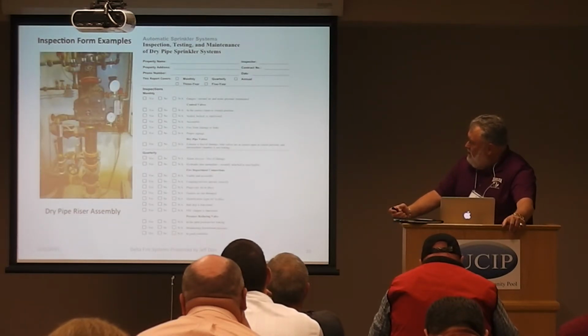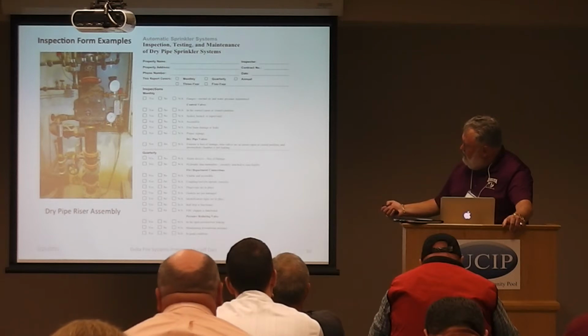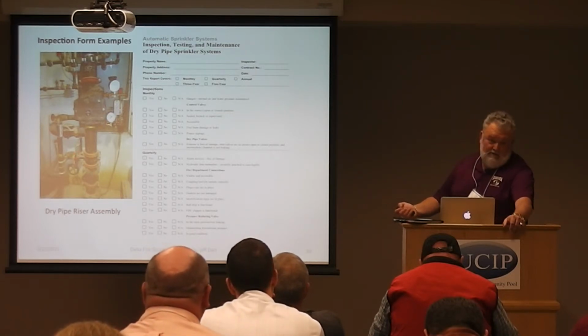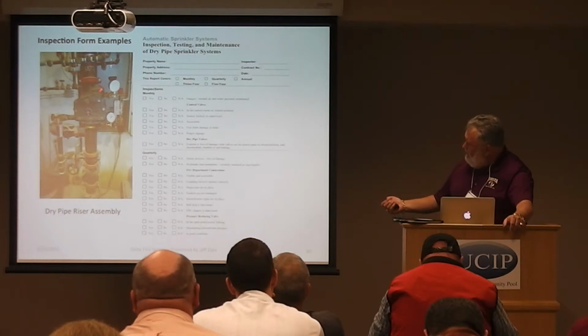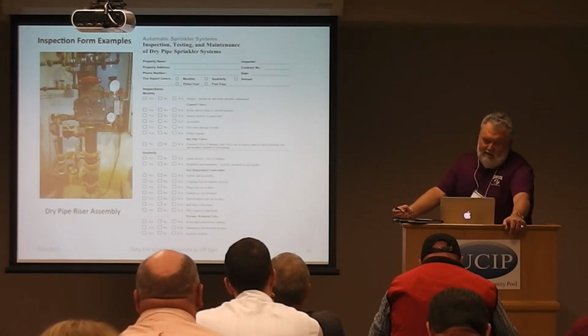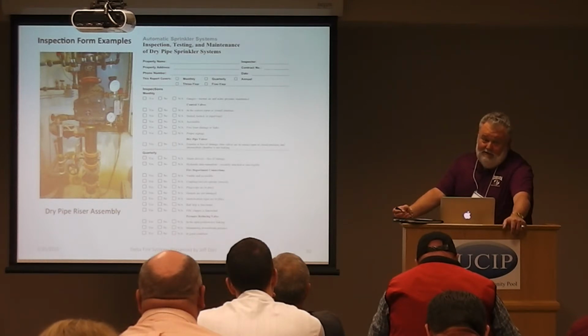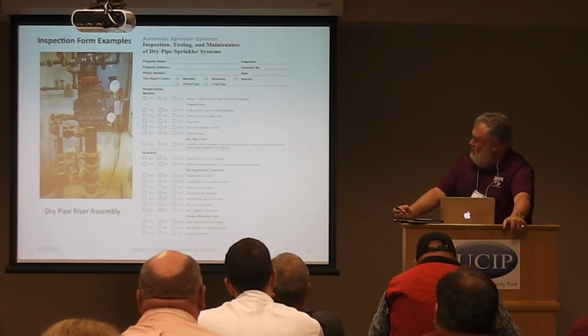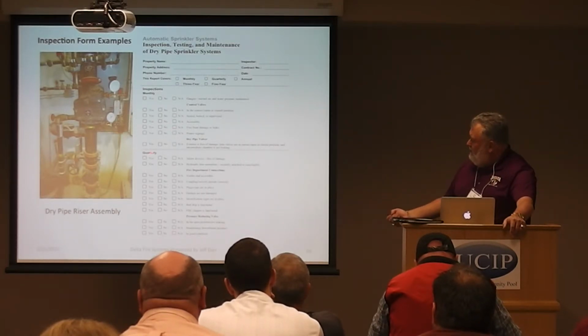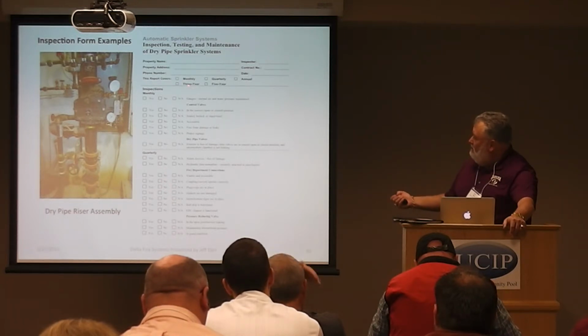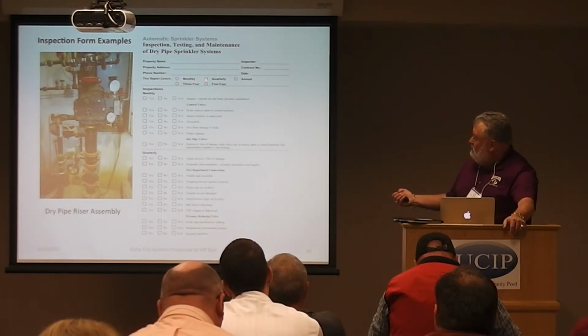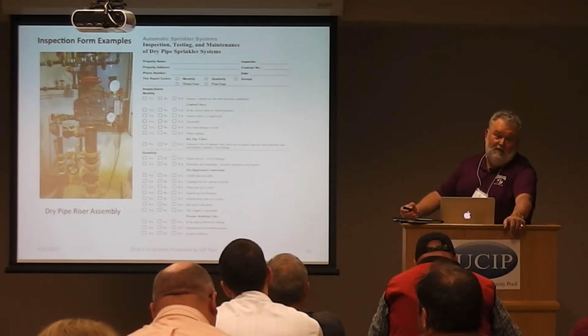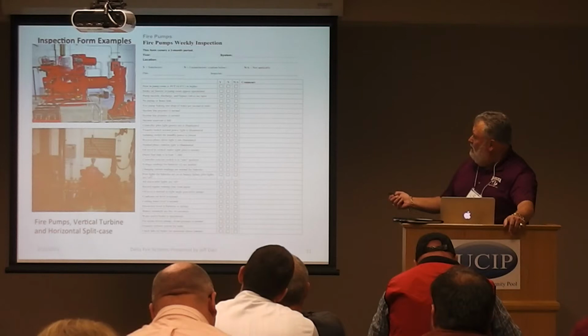Here's a dry riser, and on this one you really can't see too much from this angle, but that valve is closed. You can see that the pressure on here is actually up. I think at this point we were actually out doing an inspection, that's why that valve was turned off. But again, we've a number of times gone onto a job site and found that those are closed. And it's laid out in the same format. Here's your monthly inspections, your quarterly, and up here it's telling you whether it's a monthly, quarterly, annual, 3 or 5 year inspection. Generic form here.